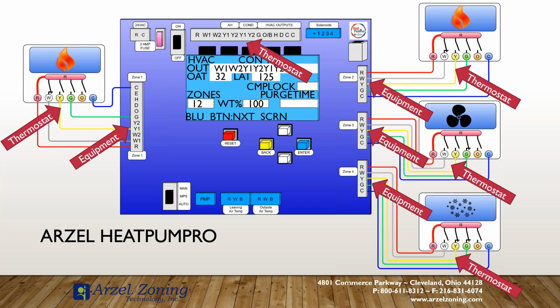So that's where we look at that line that says out. If it is listed on that output line, it is energized going to your furnace. We look at it where it says zones. That tells us exactly what zones are being serviced. So when we look at this, if we don't see our thermostat calling listed in the zone box, that thermostat's not receiving its call.